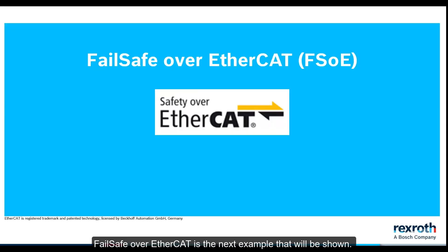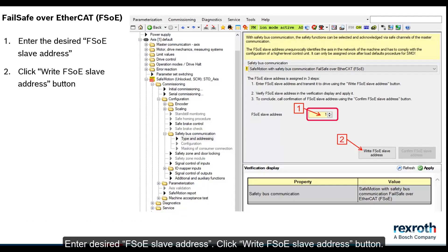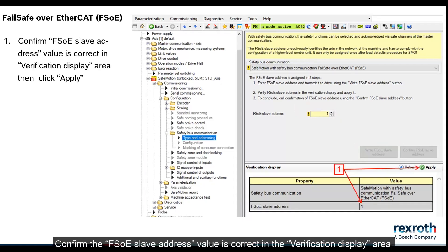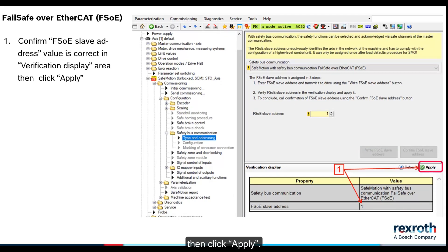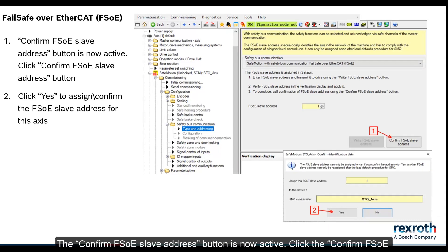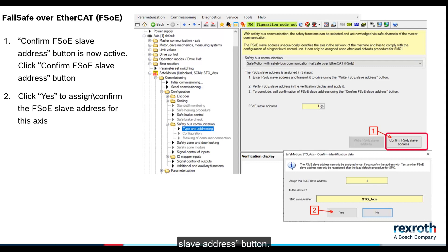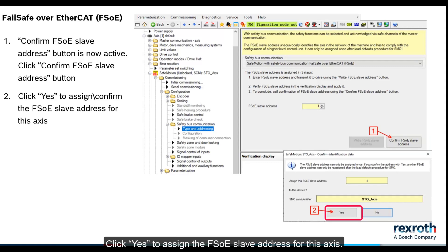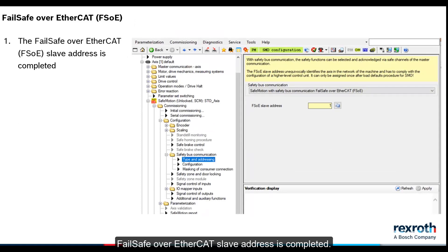Failsafe over EtherCAT is the next example that will be shown. Enter the desired FSOE slave address. Click write FSOE slave address button. Confirm FSOE slave address value is correct in the verification display area, then click apply. Confirm FSOE slave address button is now active. Click confirm FSOE slave address button. Click yes to assign FSOE slave address for this axis. Failsafe over EtherCAT slave address is completed.